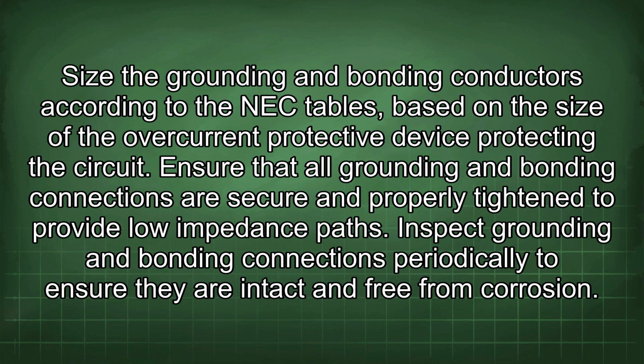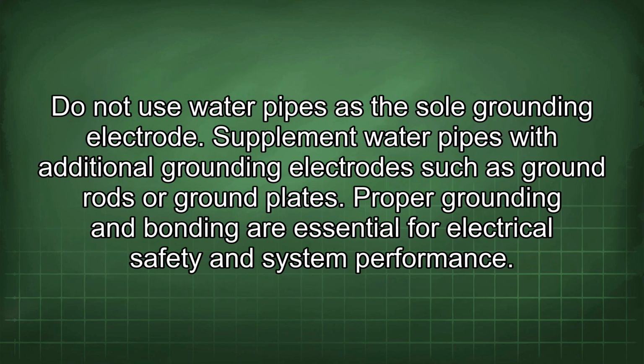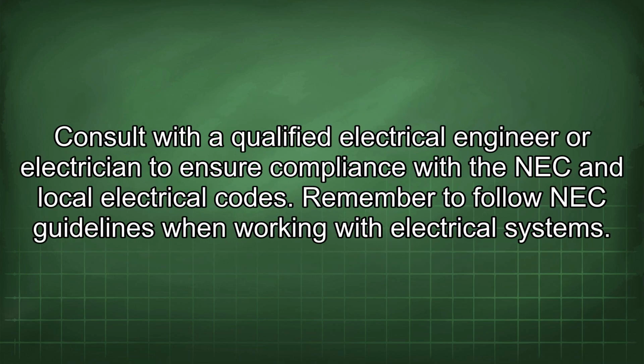Inspect grounding and bonding connections periodically to ensure they are intact and free from corrosion. Do not use water pipes as the sole grounding electrode. Supplement water pipes with additional grounding electrodes such as ground rods or ground plates. Proper grounding and bonding are essential for electrical safety and system performance. Consult with a qualified electrical engineer or electrician to ensure compliance with the NEC and local electrical codes. Remember to follow NEC guidelines when working with electrical systems.